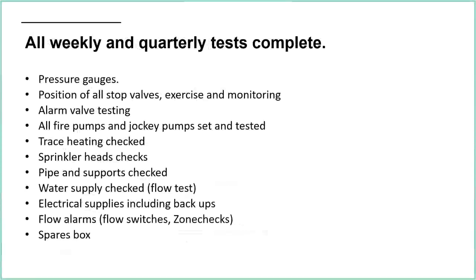All weekly and quarterly tests complete. So this is just a reminder, really, of what that entails. All the pressure gauges checked, position of all stop valves, exercising the valves, and the monitoring. So any monitored valve, then again, you need to be checking that the signals are coming through. Testing of all the alarm valves, all the fire pumps and jockey pumps set and tested.